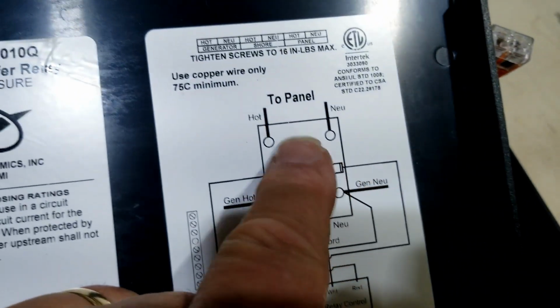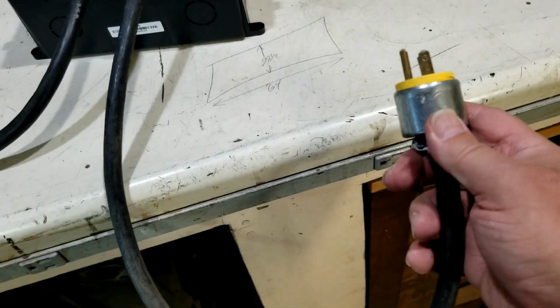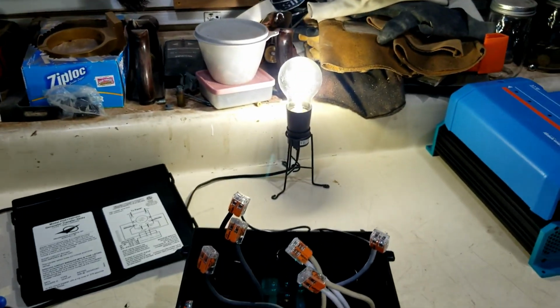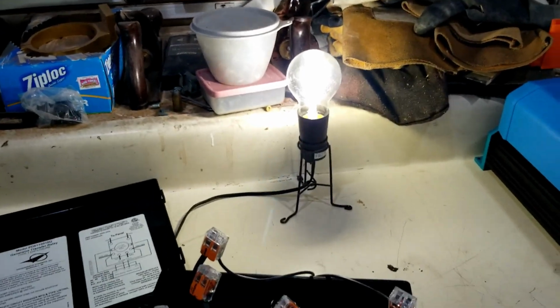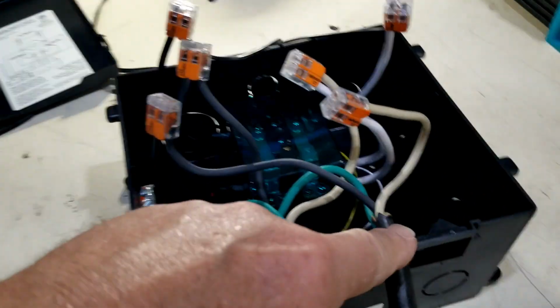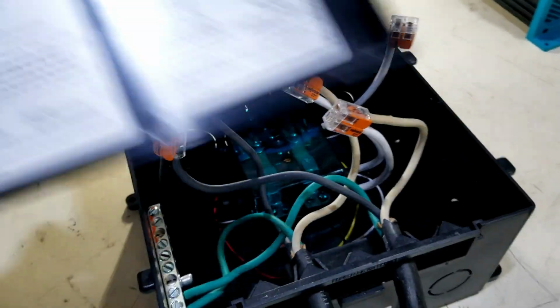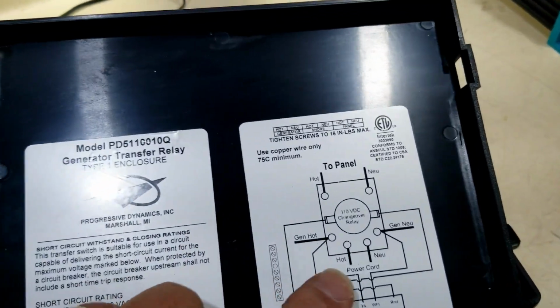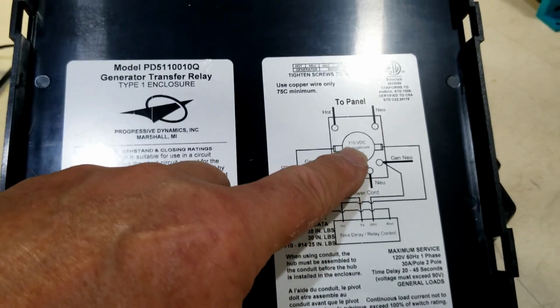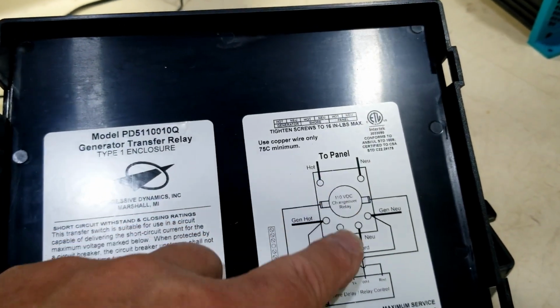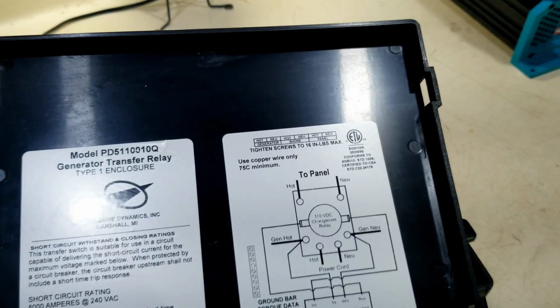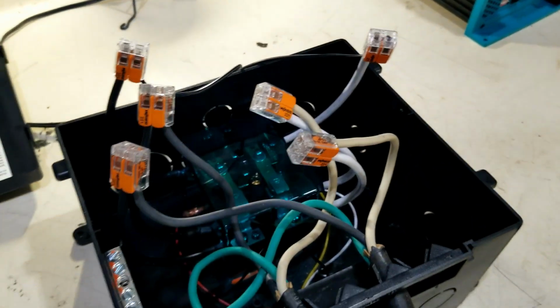So then the output, where it shows To Panel, I've connected to that light. So I'm going to plug in the one that says power cord, and you can see that my light lights instantly. The reason for that is that circuit, I'm going to go back to this, the power cord circuit goes straight through the contacts to the panel and doesn't require that the relay energize.